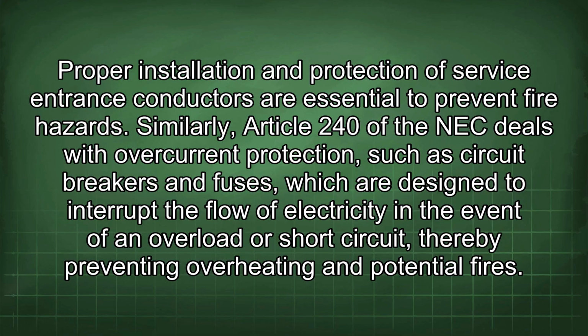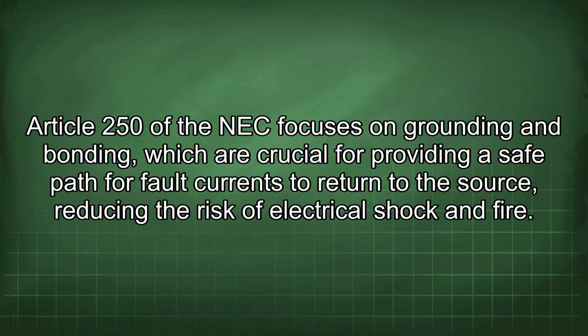Similarly, Article 240 of the NEC deals with overcurrent protection, such as circuit breakers and fuses, which are designed to interrupt the flow of electricity in the event of an overload or short circuit, thereby preventing overheating and potential fires. Article 250 of the NEC focuses on grounding and bonding, which are crucial for providing a safe path for fault currents to return to the source, reducing the risk of electrical shock and fire.